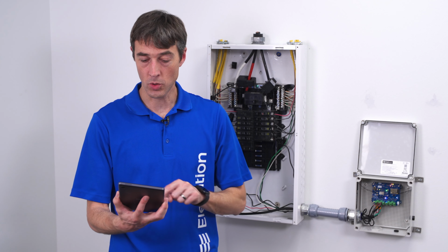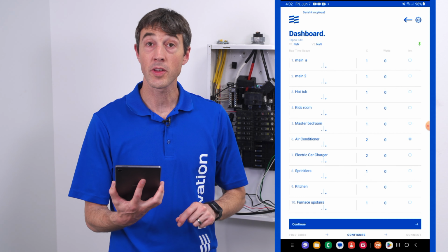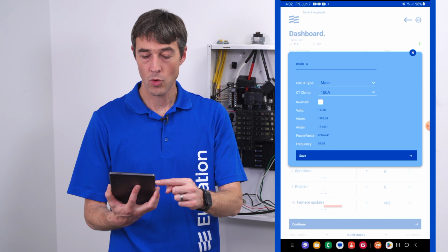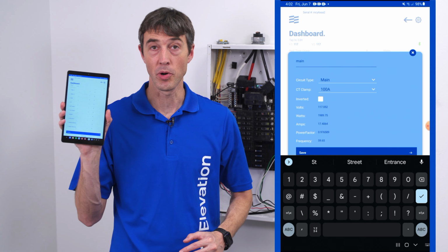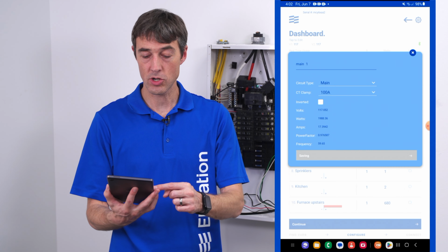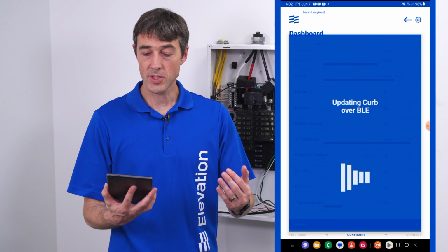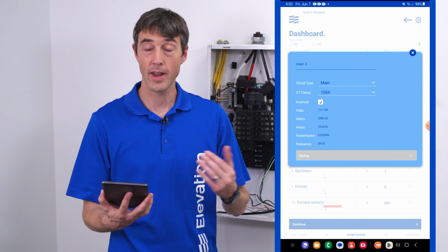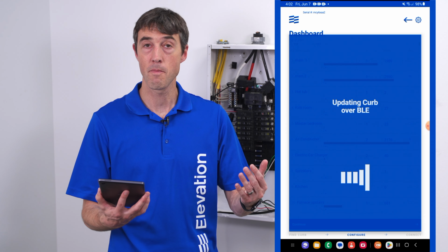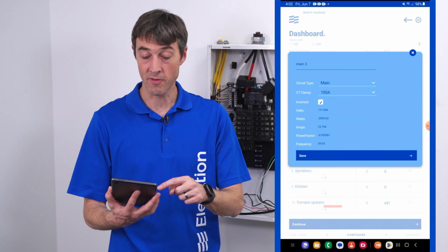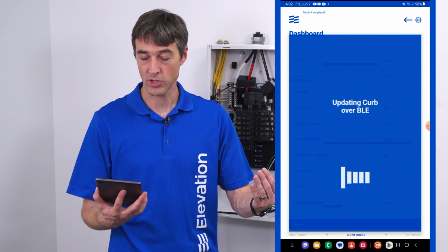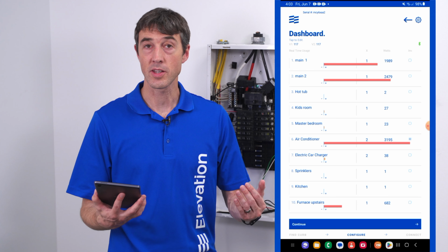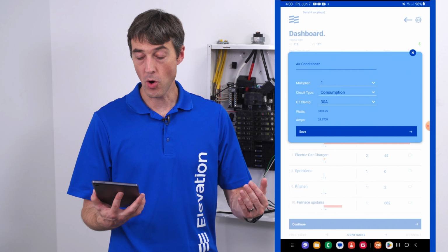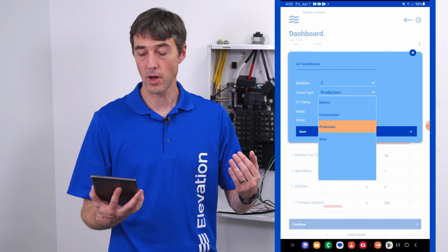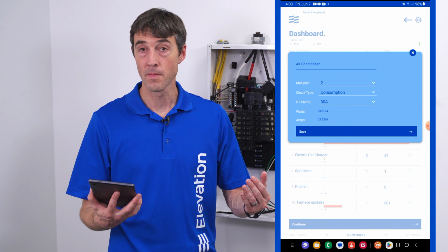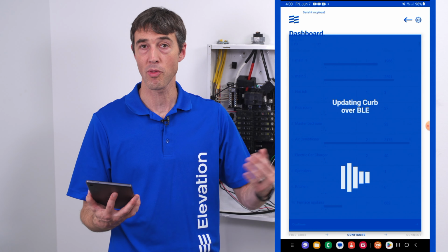Once you've identified the individual Curb serial number, you're able to go to the configuration page. The configuration page will allow you to rename each of the individual inputs from the mains, solar, air conditioner, air handler, etc. This also allows you to configure the mains and allows you to invert the mains so that they are measuring the right direction. It allows you to invert the solar so that it is also going the right direction. It allows you to double power consumption readings for 2-pole breakers. Most 2-pole breakers are a balanced load, which means that you can double the power consumption of an air conditioner to get both legs of that power consumption.